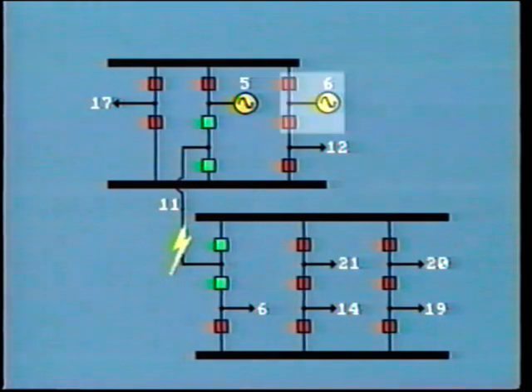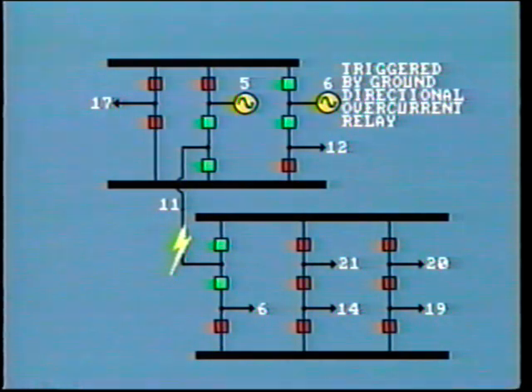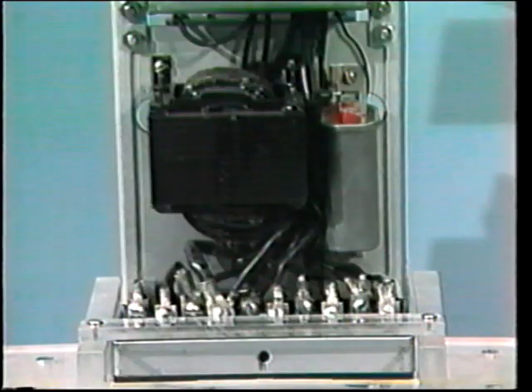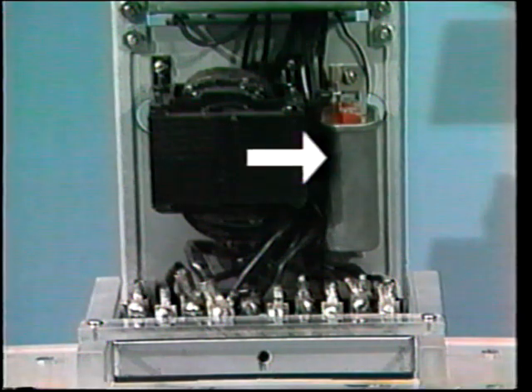However, what was not correct was the tripping of the number 6 generator. This misoperation trip was triggered by operation of the generator ground directional overcurrent relay. Subsequent investigation of this relay showed that a capacitor in the voltage polarizing circuit had failed. So the relay, in effect, had lost its sense of direction. Now, we don't know whether the capacitor failed at this particular fault occurrence, or perhaps the relay had been sitting in this ineffective condition for some period of time. If the fault had not occurred, the problem with the capacitor would no doubt have been discovered only during the next routine test.